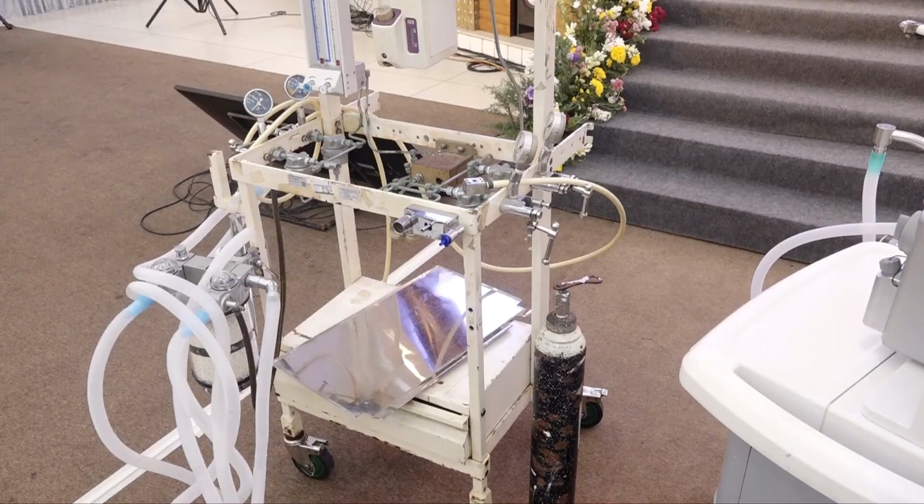Then you may ask me, so why should I close the cylinder? Let me keep the cylinder open. The problem is, there can be a lot of fluctuations in the pipeline pressure when you are using it. Because you have started with 1 OT, after some time, 10 OTs have started. In the ICUs also, 10 patients have been connected to the same pipeline source of oxygen. So the pipeline pressure in the workstation starts fluctuating.